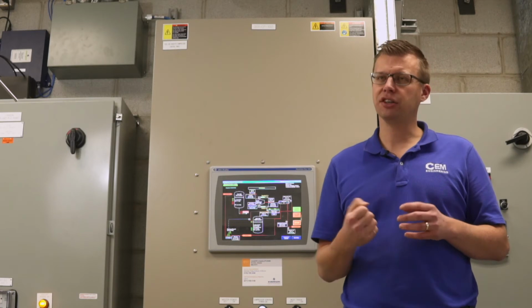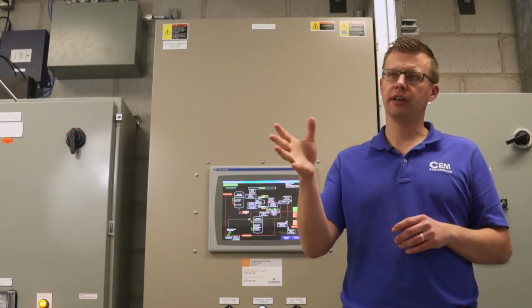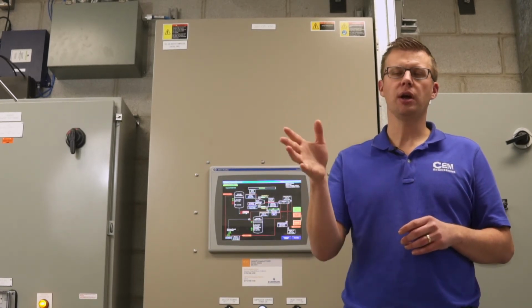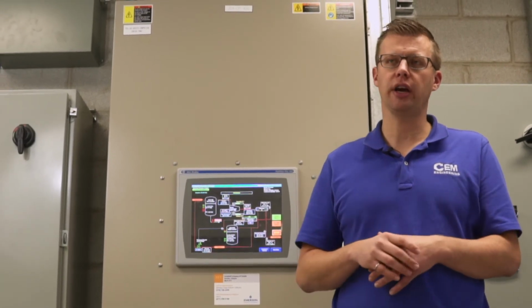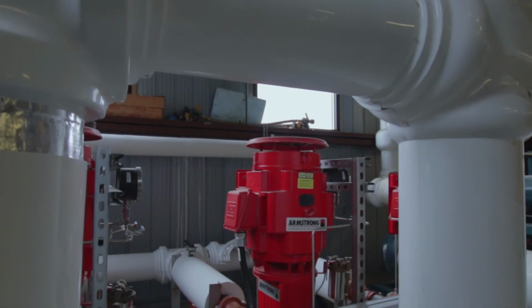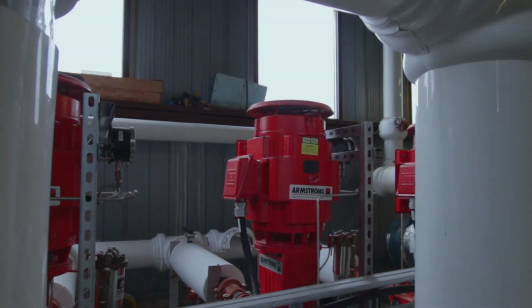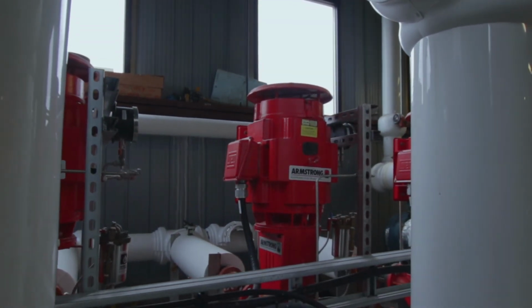Additionally, to drive a more efficient system, we tied into the existing condensing economizer here. It's rated for about 6 million BTUs per hour of heat recovery, and it takes the hot exhaust gas, what energy is left in it after the boiler, it takes it out and draws out additional energy and makes hot water for the heating process of the soup, but also space heating and things like that. So it's a neat add-on to a Co Gen that drives even more overall system efficiency, causes more natural gas savings, and drives more money back into the operation.